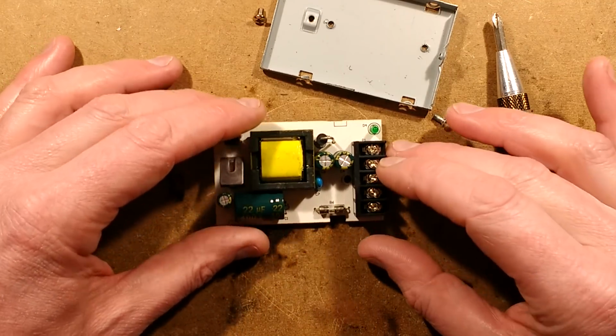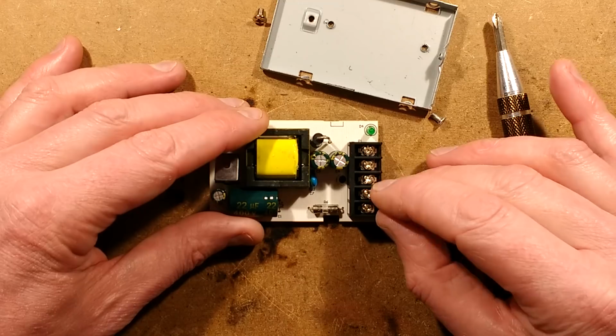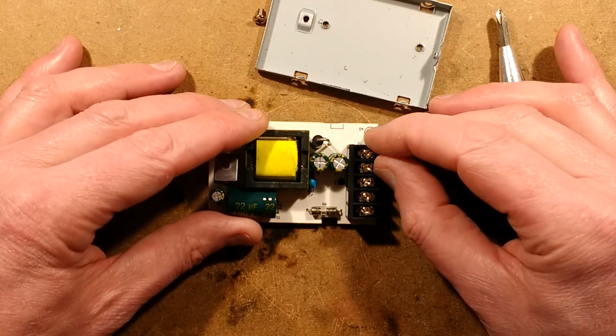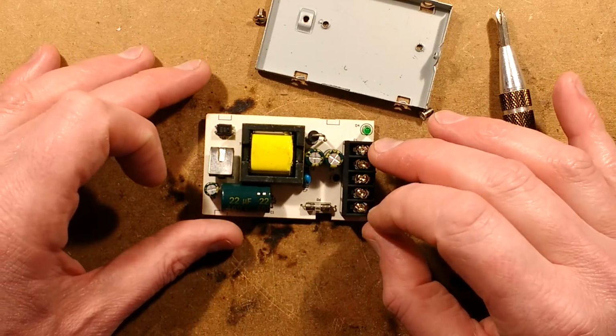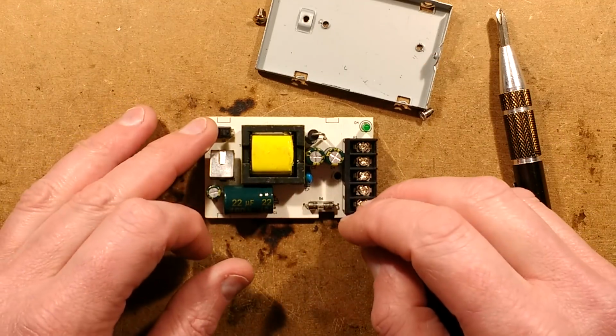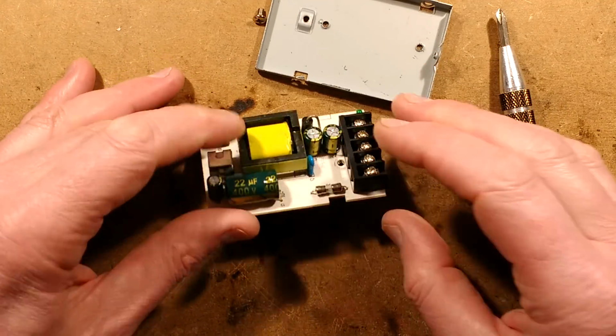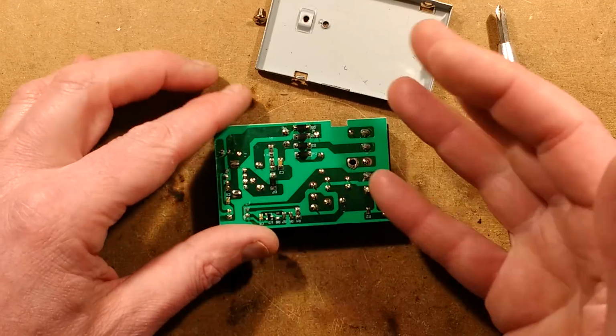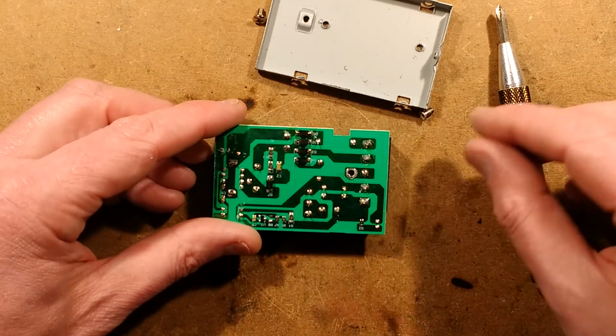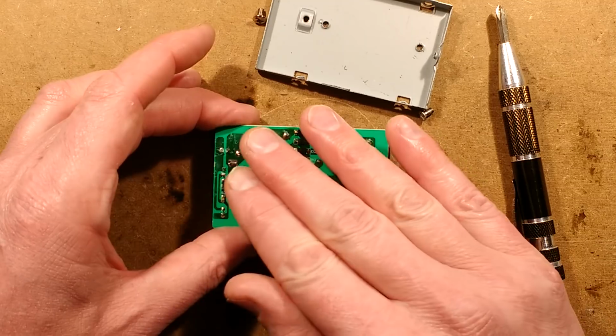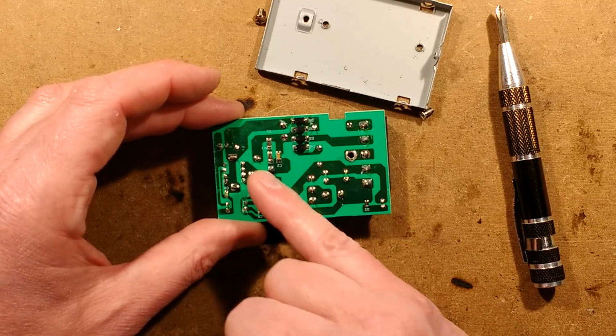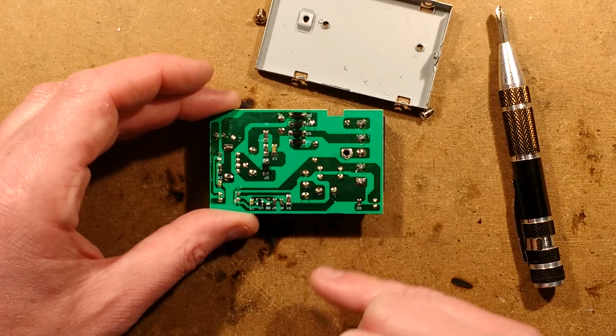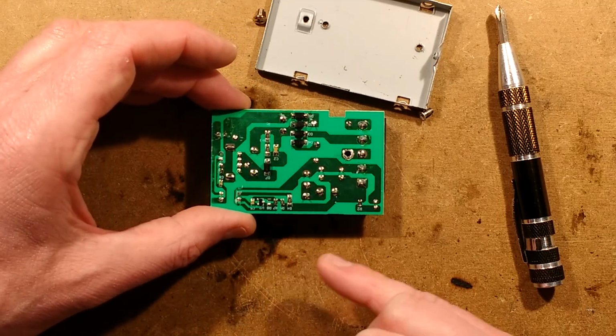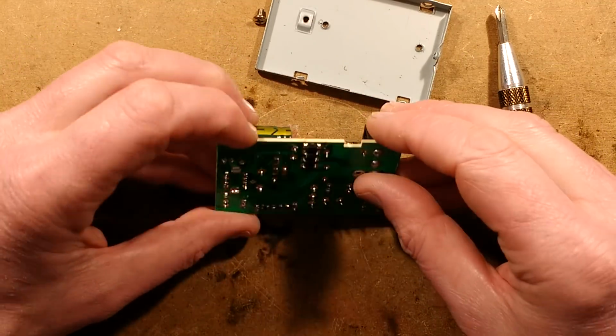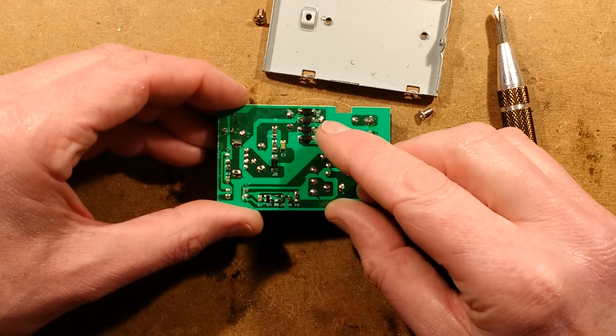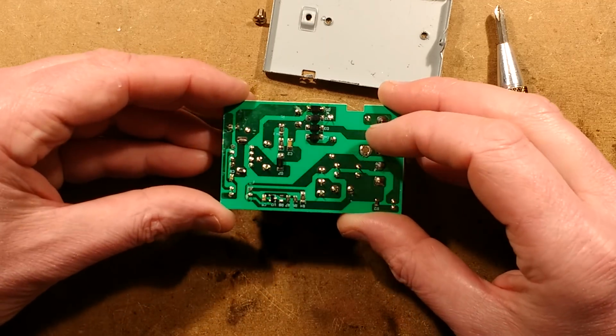It's worth mentioning that when you're testing from input to output, you have to bridge the positive and negative together, and the live and neutral together. The reason is, if you just connect at one of the terminals, you're going to stress all the components in the vicinity - these rectifiers are going to see 2000 volts or something like that. So you have to bridge them together so they're bonded to the same potential in the circuitry, and then it will find the easiest route through the winding. In this case, it would be the positive here. Where is the winding of the transformer?